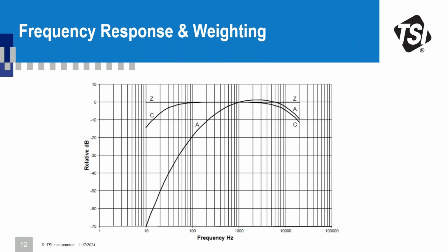So we ought to know what are the frequencies that we want to prioritize, and what are the ones that we want to discriminate against, right? And that's where the weighting curves come in. So think of them as weights, but they're frequency weights. So you measure sound with no weight, which is Z weighting, and then you apply an A curve to it. The A curve is going to come in and discriminate against the very low frequencies, right? And give you just the upper higher frequencies.